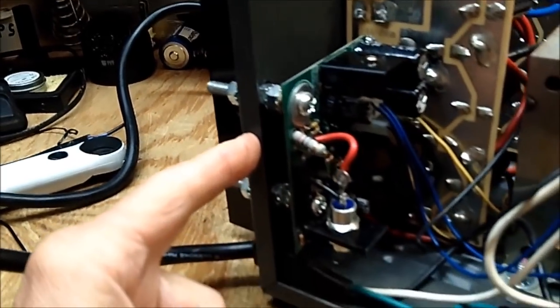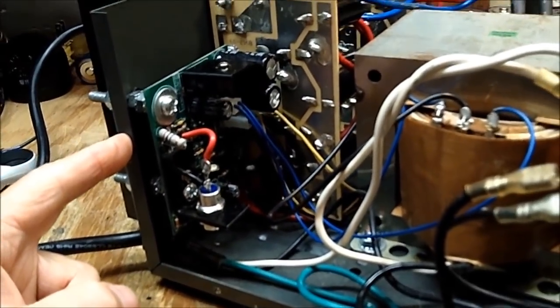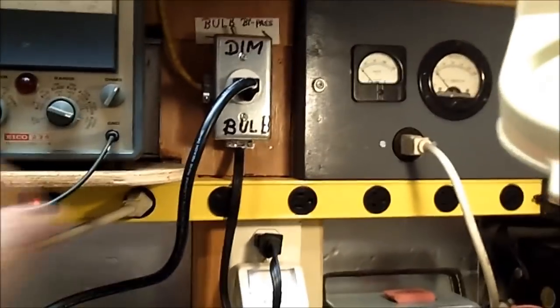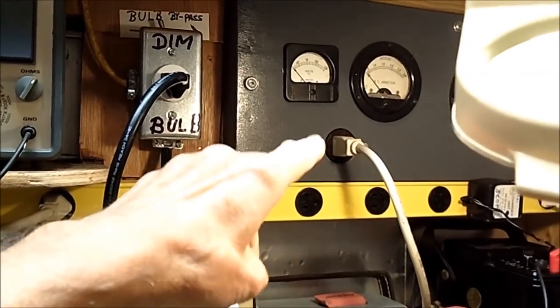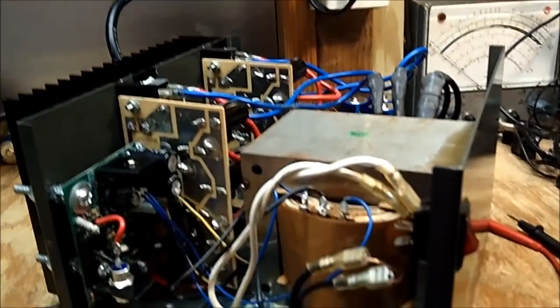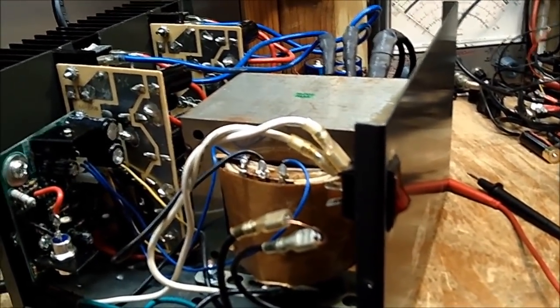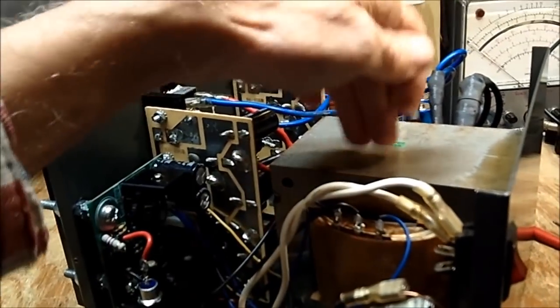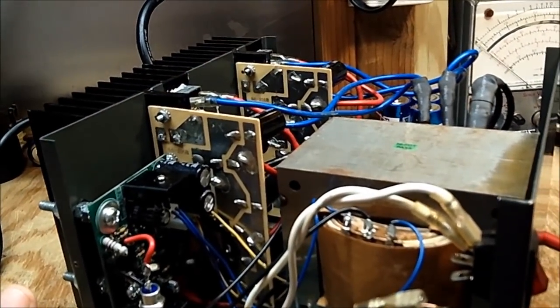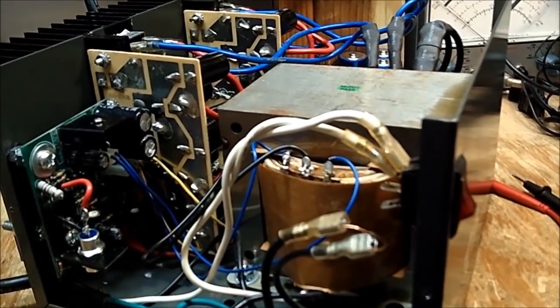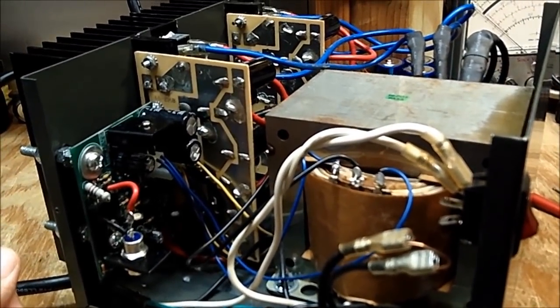So we can put a meter across this now. I don't want to throw the bypass yet. I can't run it through my variac. That's only got a 3 amp fuse in it because it's good for 3 amps, and it's going to take supposedly 15 amps, but there's a surge. And even though there's not any load on it, it's going to take a surge because it's such a massive power supply. It's not going to be just a few milliamps.